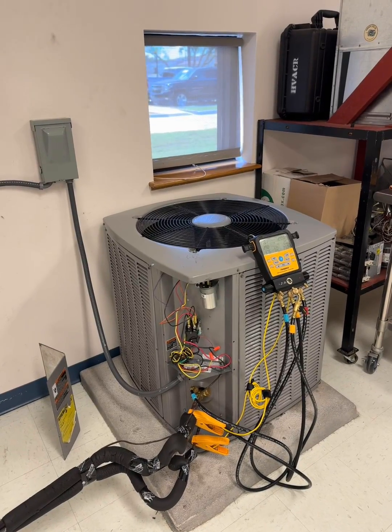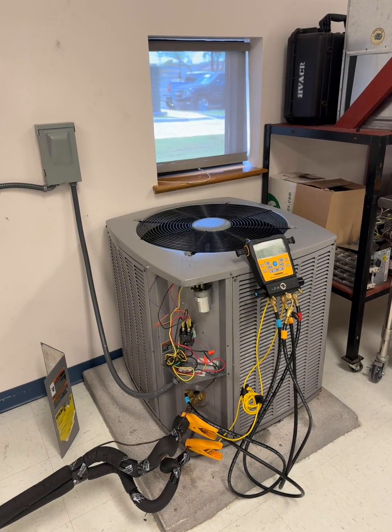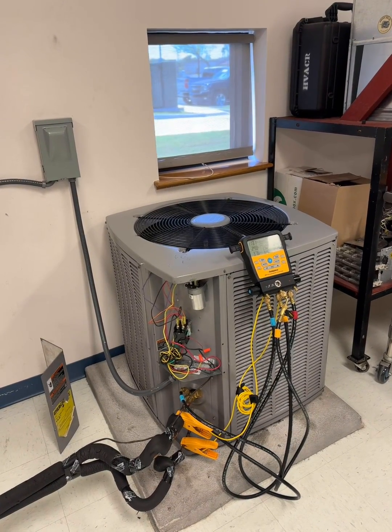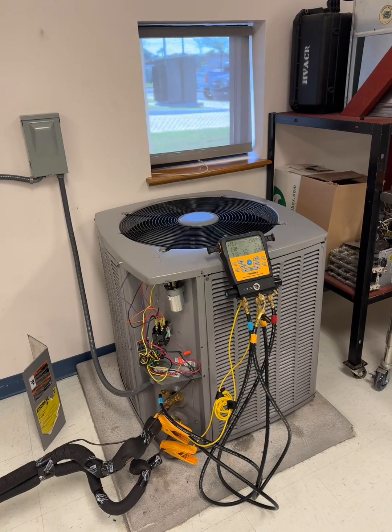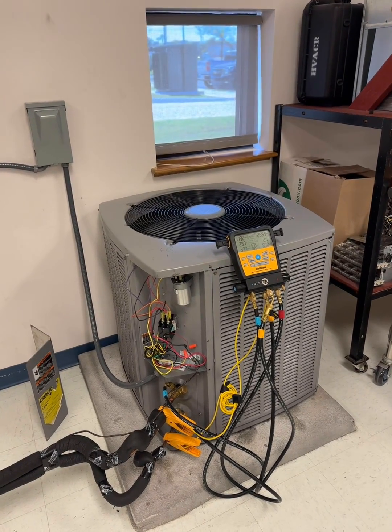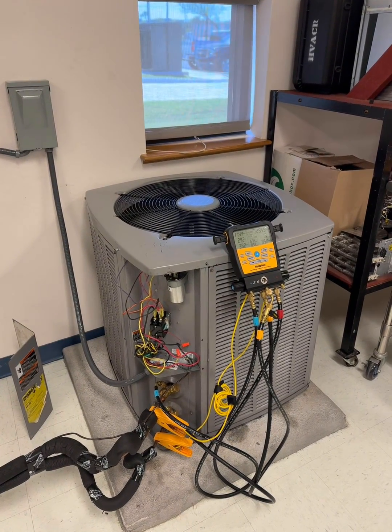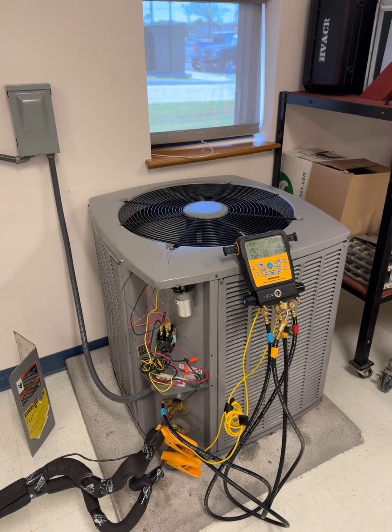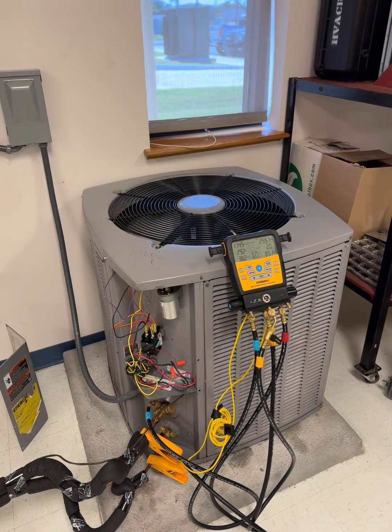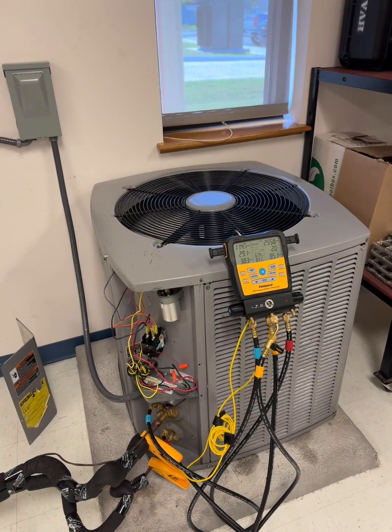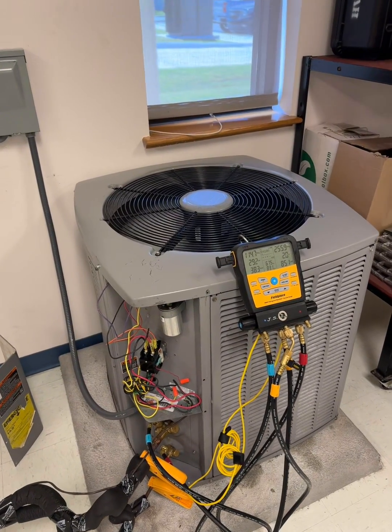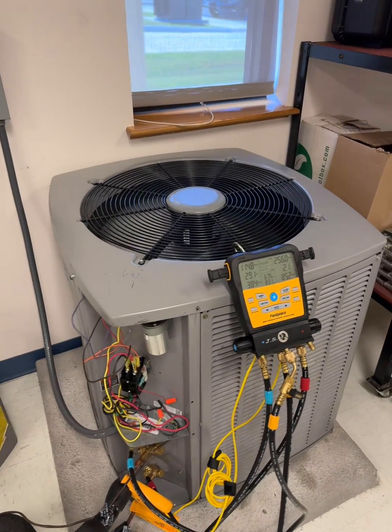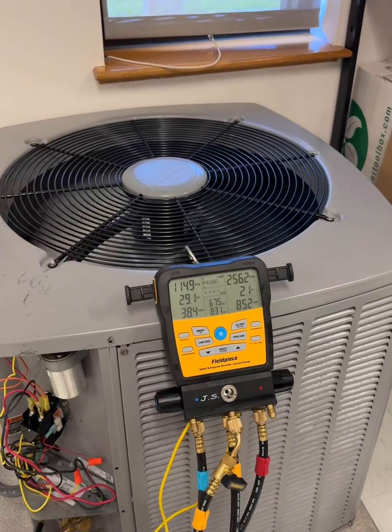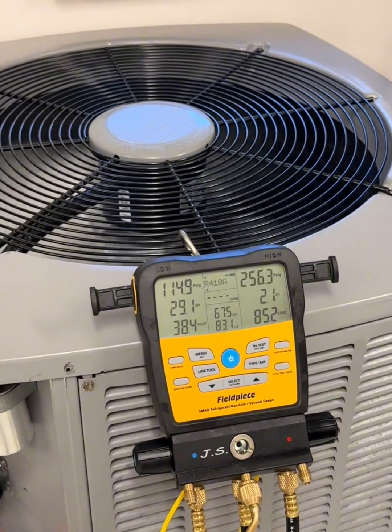How a typical split system works. A split system is the most common type of residential HVAC system, made up of two main parts: an outdoor unit, or condenser, which contains a compressor and condenser coil, and an indoor unit, or air handler, which contains the evaporator coil and blower. These two parts are connected by refrigerant lines.